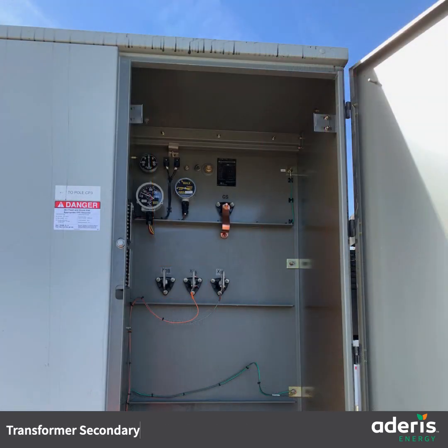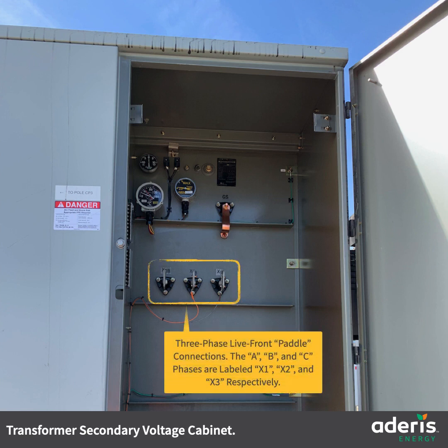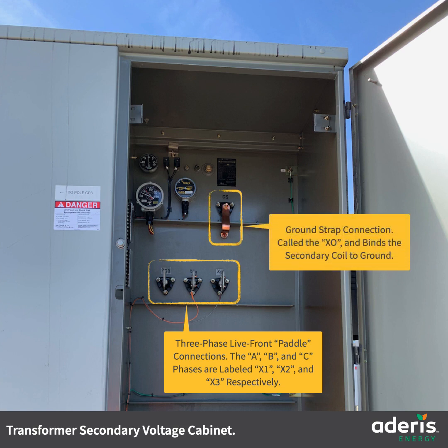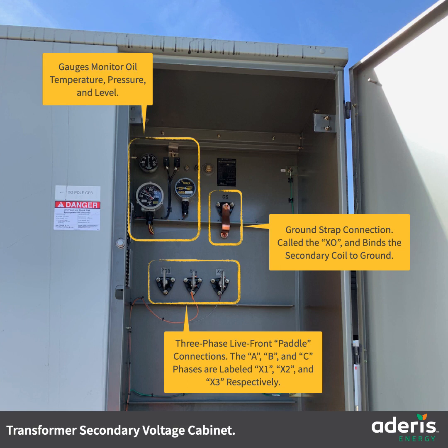Transformer secondary voltage cabinet. Three-phase live front paddle connections. The A, B, and C phases are labeled X1, X2, and X3 respectively. The ground strap connection, called the XO, binds the secondary coil to ground. Gauges monitor the oil temperature, pressure, and level.